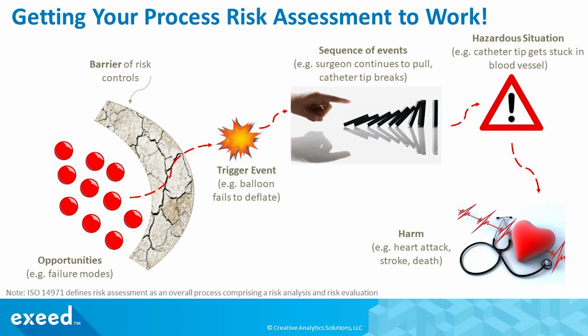It may be because of several failure modes, not just one. Once it happens, it may lead to a domino effect. For example, as the surgeon continues to pull the catheter back, the tip breaks. This leads to a hazardous situation because the broken tip now can get stuck and block the blood vessel. At this stage, the patient is exposed to one or more hazards of surgery, which may lead to one or more harms of different severities.